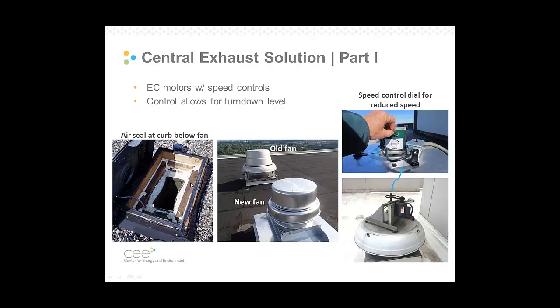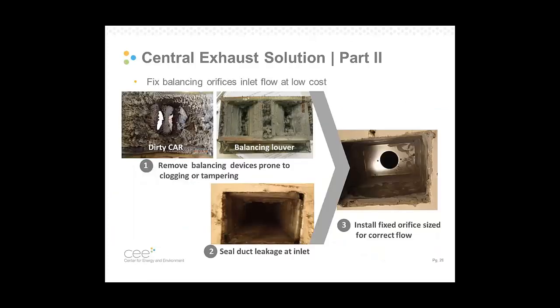The other detail at the rooftop is this detail here on the left where we're sealing the curb below the fan. So this is the duct coming up, and the bottom of the fan is tipped up here. You can see that there's foam here that's sealing the gap so that all of the air the fan is drawing in or exhausting is coming from the duct and not from unintended places like the roof cavity. So that's the rooftop detail.